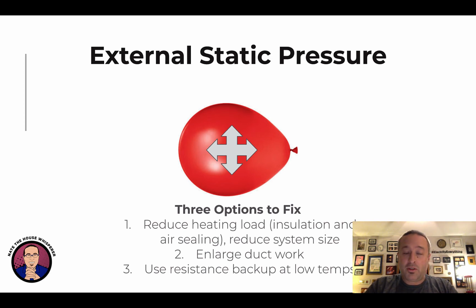The third thing is you use resistance backup at low temperatures. So say you have a 4-ton load house, but you only have 3 tons of ductwork. You put a 3-ton unit in, and use resistance to make up the difference in very cold weather. It's a tool.